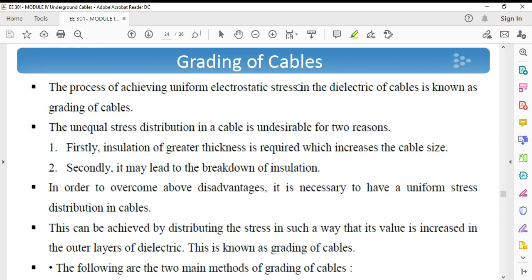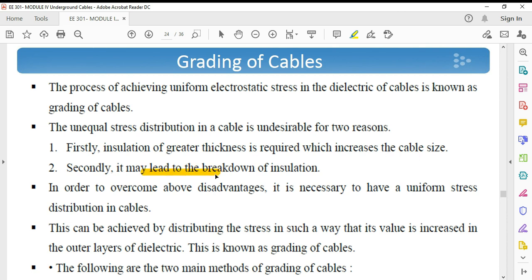First is grading of cable. In the last class we have seen that for a cable, the potential stress is maximum near the conductor and minimum near the sheath. So there is a variation in potential difference across the insulation of the cable. Due to this unequal distribution, there are two disadvantages: insulation of greater thickness is required, which increases the cable size, and it may also lead to breakdown of insulation. So we do grading of cables.